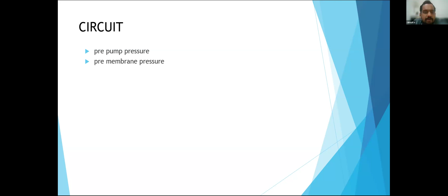It should be a pre-pump pressure, called P1, or it might be a pre-membrane pressure called P2, or a delta pressure, the difference between P2 minus P3. P3 is nothing but your post-membrane pressure. So delta pressure is the difference between the pre and the post.